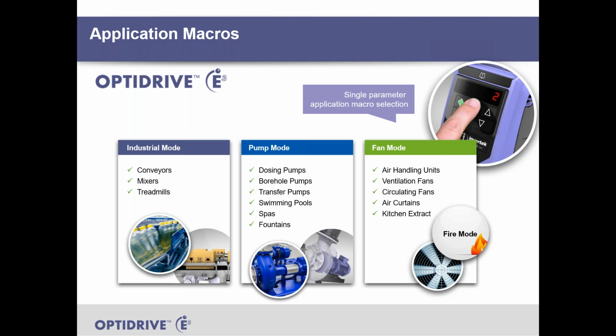In the drive itself, we have 3 modes. We have an industrial mode, so that is designed for constant torque applications like conveyors, mixers, treadmills, those kind of applications. We have pump mode, so for dosing pumps, borehole pumps, transfer pumps, those kind of applications. We do a lot of decorative fountains and things like that with the E3.